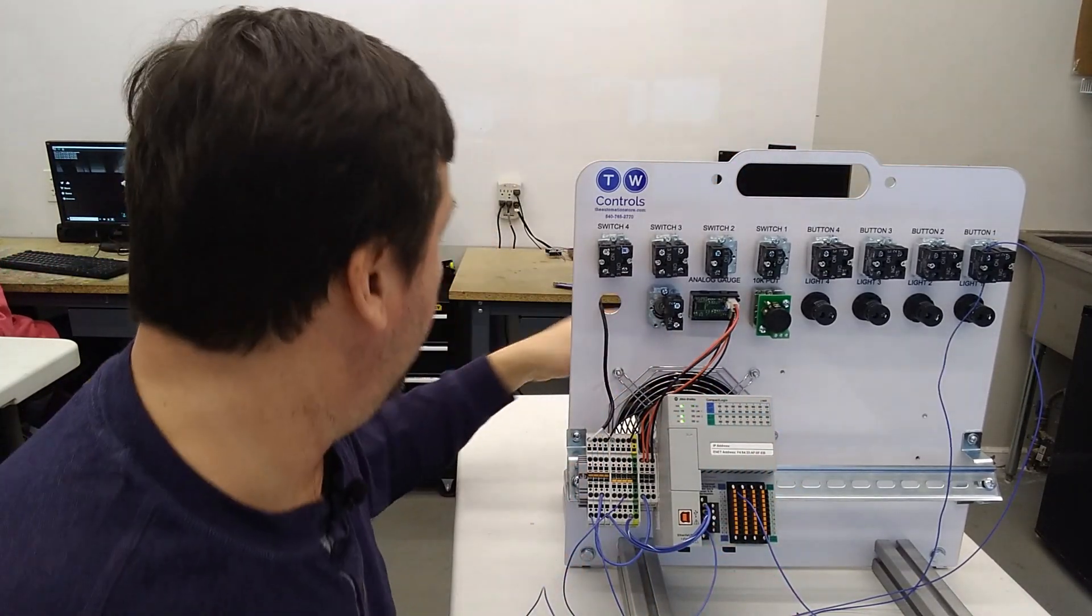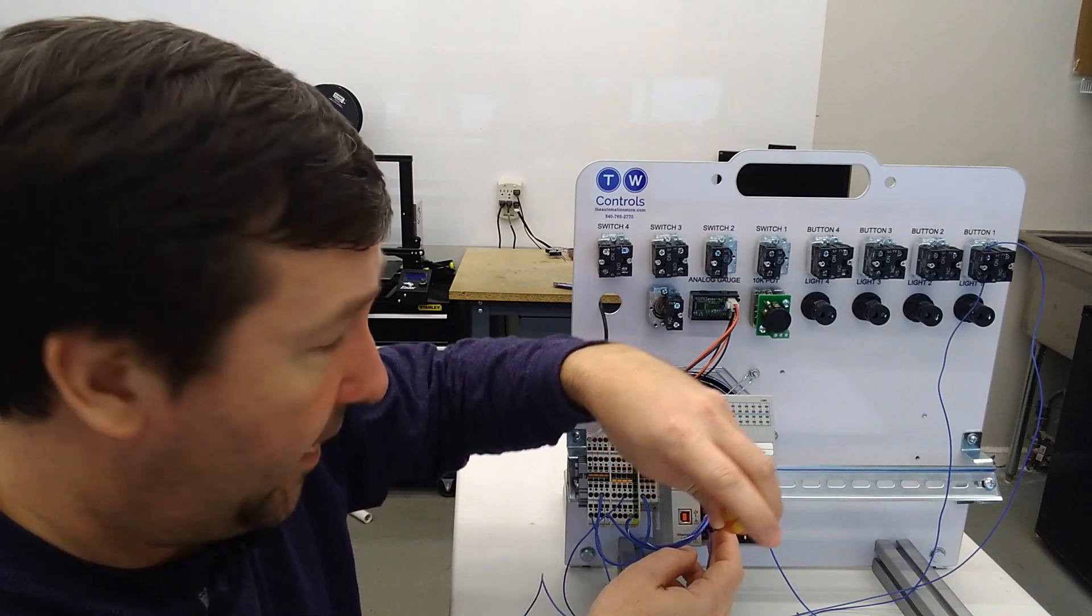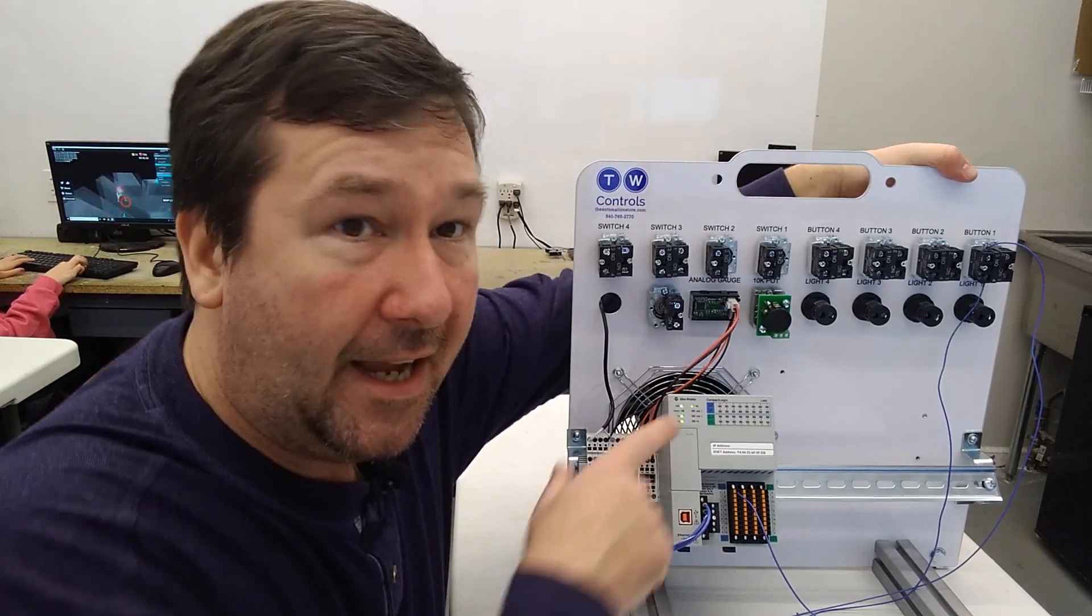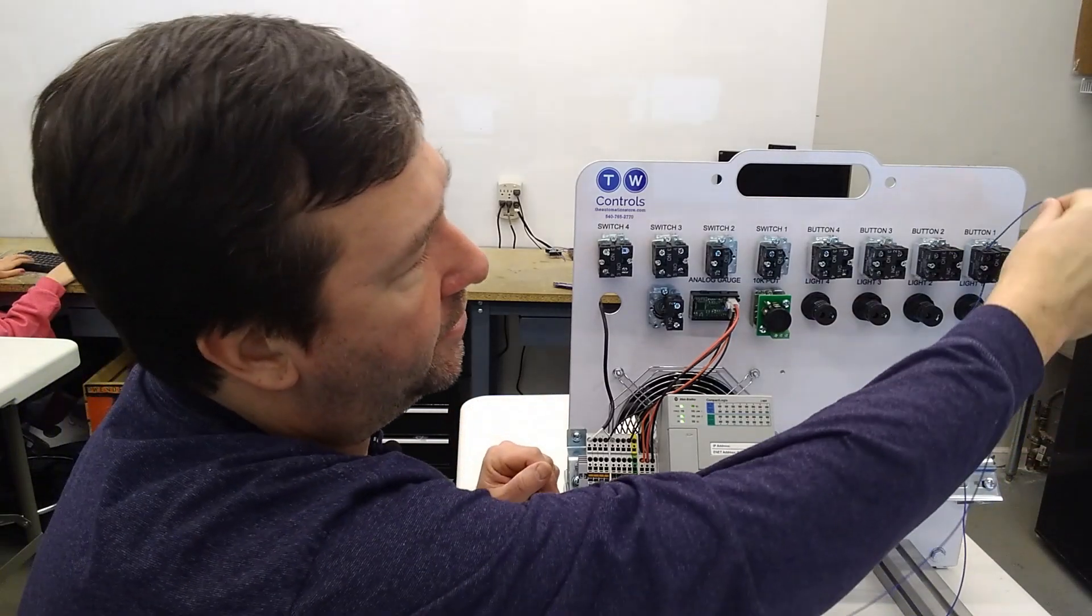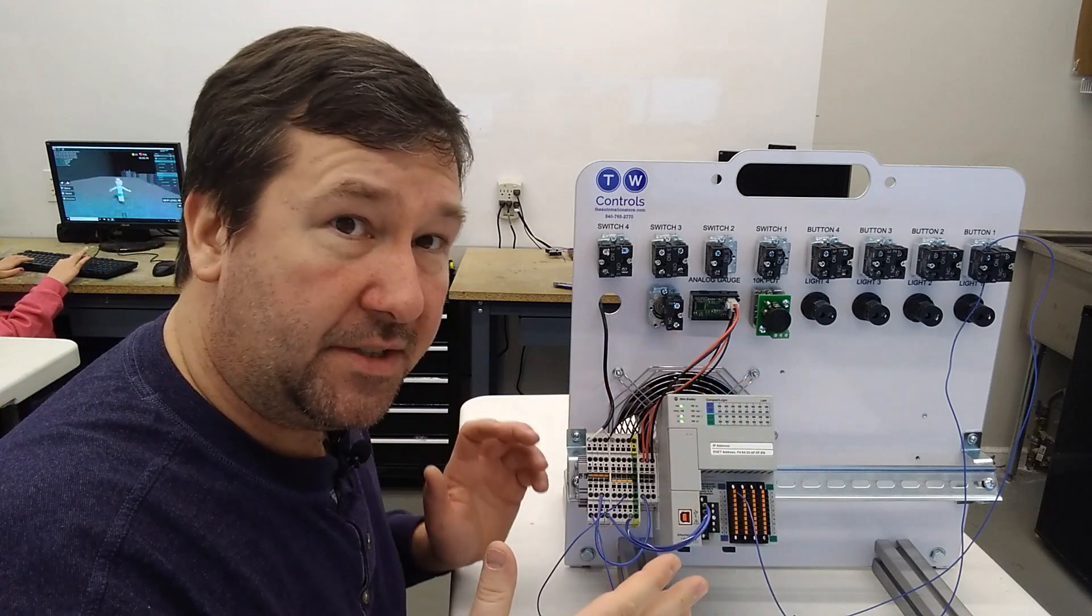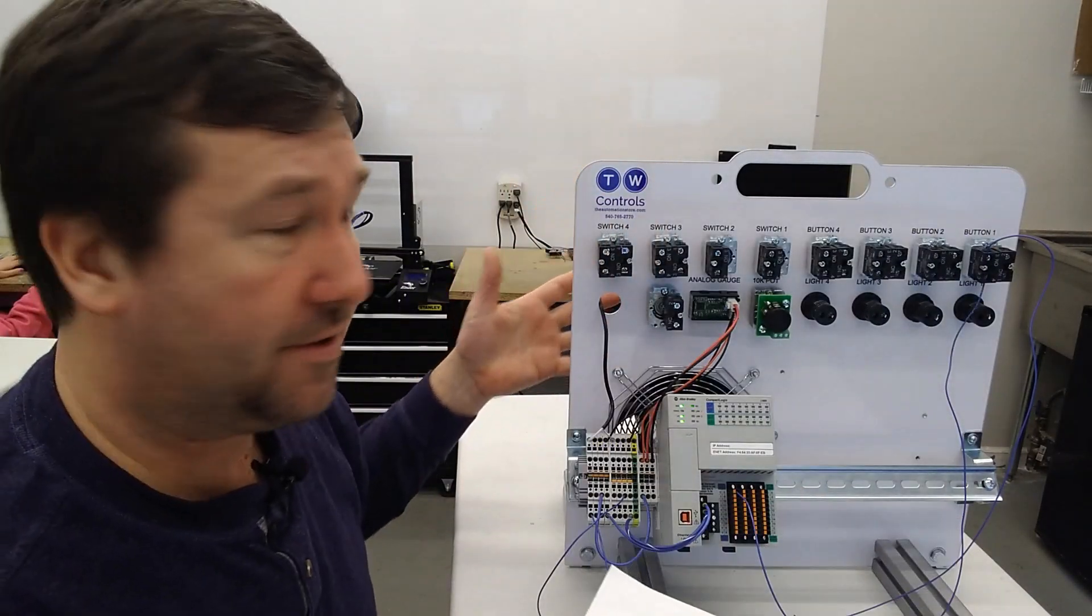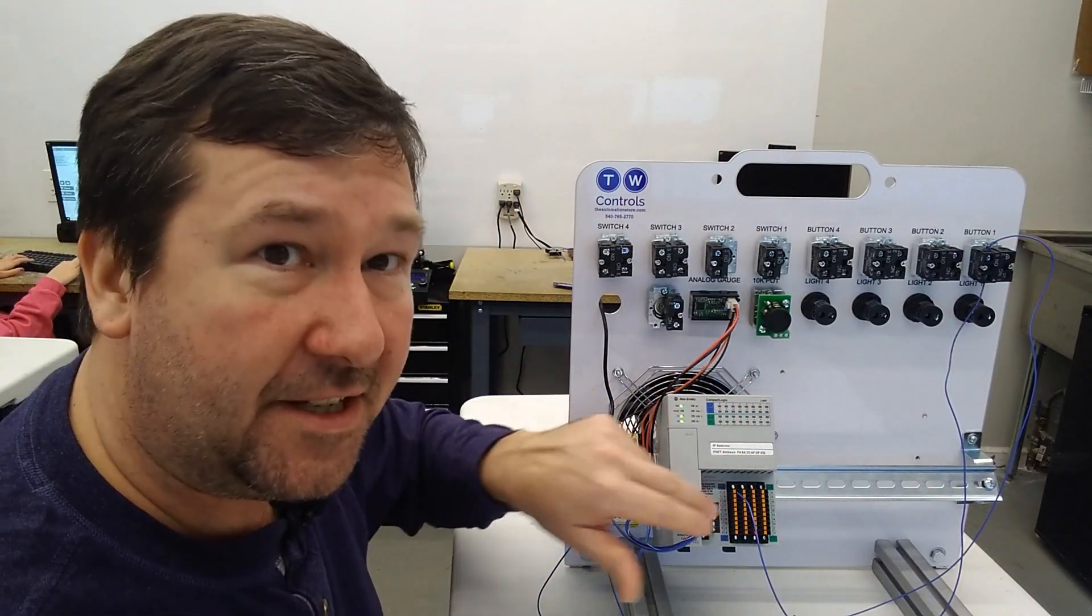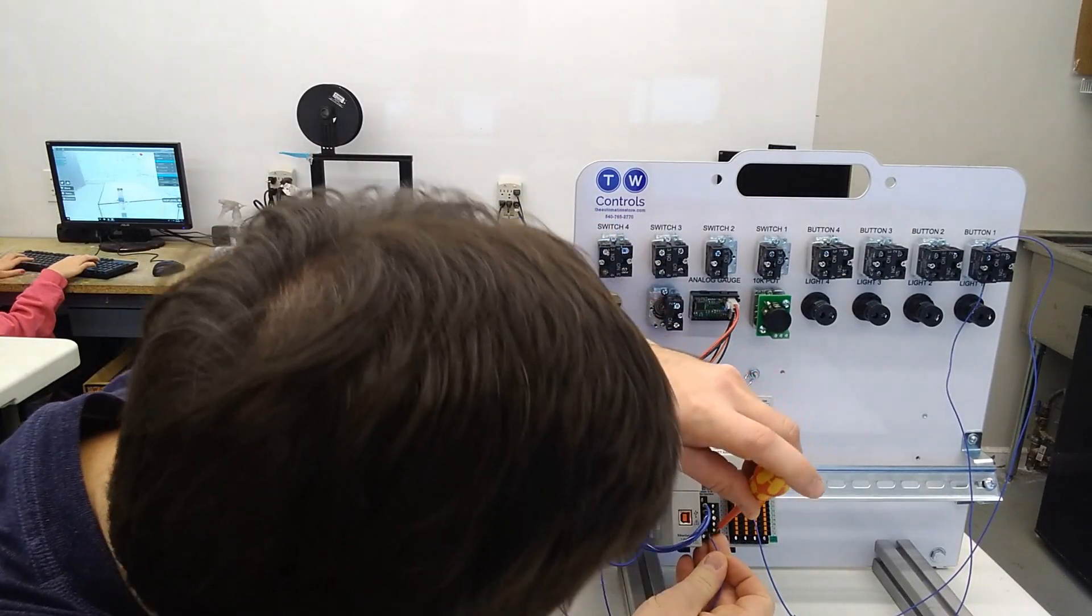let's take this FP minus terminal loose just so you can understand what I was talking about, about the circuit not being complete. So we've taken that wire off and now I'm going to press button one and we're not getting input zero. So in this case, we have power from the plus of our 24 volt going to the top of our green contact and then out of the bottom of our green contact, we're going to input zero. But we don't have that last little piece of our circuit. So if you have a similar situation where you're pressing the button and you're sure that the power is wired right to it, then check that common. Chances are it's going to be the issue.